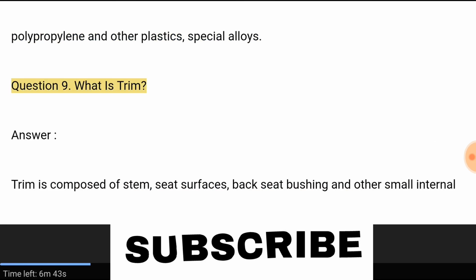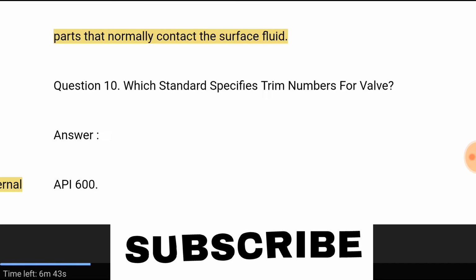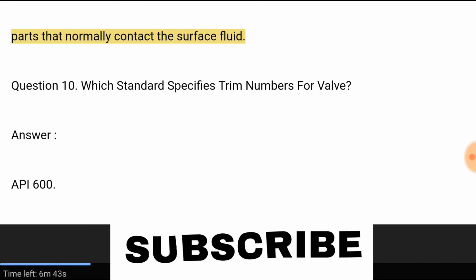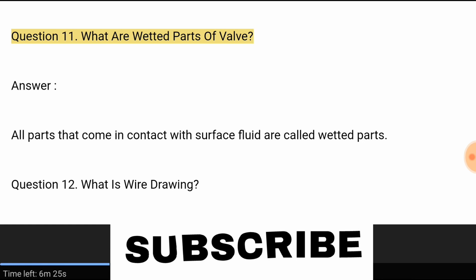Question 9. What is trim? Answer. Trim is composed of stem, seat surfaces, back seat bushing and other small internal parts that normally contact the surface fluid. Question 10. Which standard specifies trim numbers for valves? Answer. API 600. Question 11. What are wetted parts of a valve? Answer. All parts that come in contact with the surface fluid are called wetted parts.